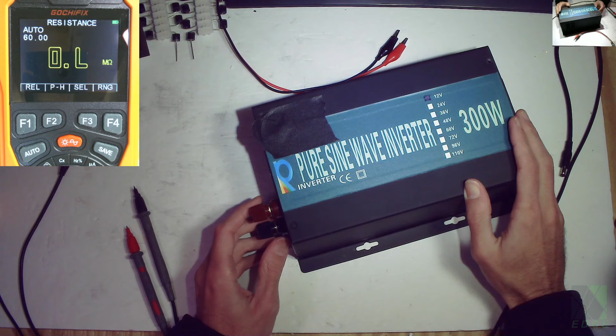I've removed the bolts off the battery terminals so I can access them with the multimeter, set to the auto resistance range in ohms. I'll probe positive and negative with my ohm meter. You're seeing the capacitors on the input charging up—hundreds of ohms, now 3 kiloohms, thousands of ohms, slowly climbing. Notice the K and ohm signs on the right-hand side—now it's up to 44 kiloohms, 44,000 ohms, and that number keeps going up.